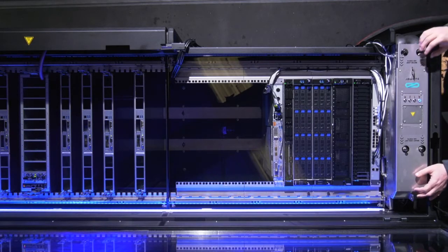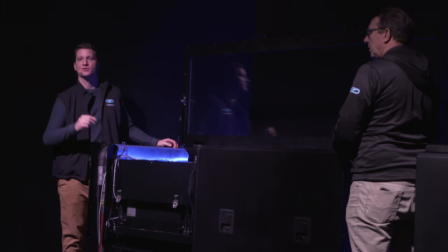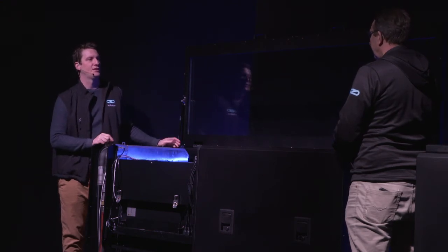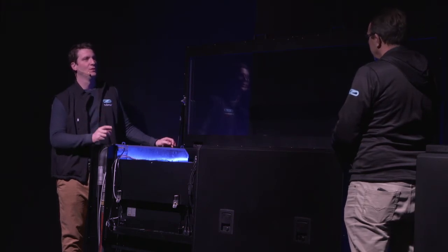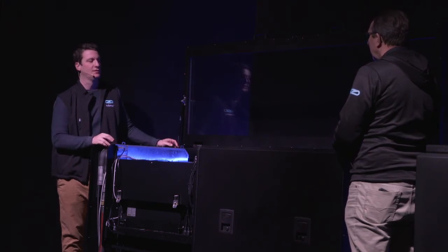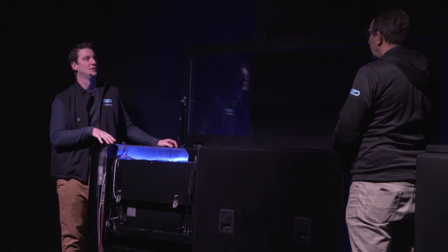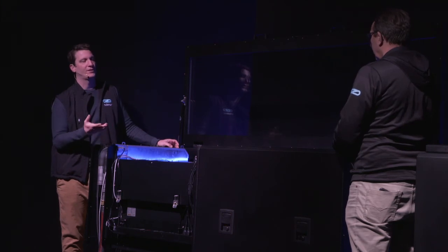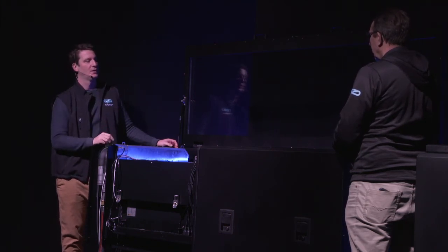Yeah, and we mentioned replacing a CDU is a 5-minute job. There's a term that we call thermal inertia, which defines the amount of time and the increase of temperature over time. Systems will typically shut down when the set point reaches around 90-95 degrees centigrade. You'll start seeing servers shut down. I guess that's a natural security measure to an issue like a full system failure. But with a fully loaded system, you typically have 30 minutes before that occurs. So you have more than enough time to replace a CDU without shutting down the system. And of course, if you have an environment where you have 2 CDUs, then you're looking at, for sure, no risk of downtime at any moment in time.